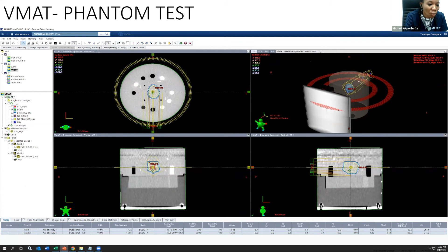Now, after this, we do absolute dosimetry. Remember, we have to do absolute dosimetry even right before the commissioning process starts, to tune and make sure everything is okay for the machine before commissioning starts. But after all this, we have to do absolute dosimetry again. The protocol we used was TRS-398. That was the protocol that we followed to carry out the absolute dosimetry.